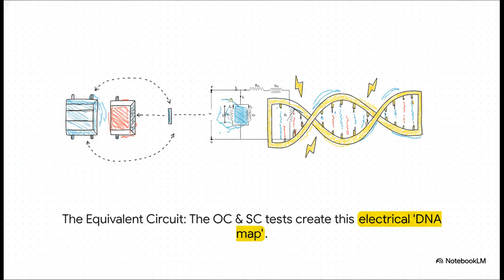But wait, what about temperature? That DNA map tells us about efficiency, but it doesn't tell us how the transformer is going to hold up after running at full blast for, say, 8 hours straight. For that, we need a long-duration stress test, and that brings us to an incredibly clever solution: the Sumpner's test. The problem, like we said at the start, is energy. Actually trying to run a huge transformer at full power just for a test is unbelievably wasteful.